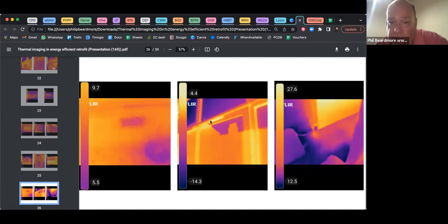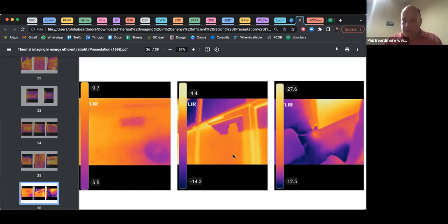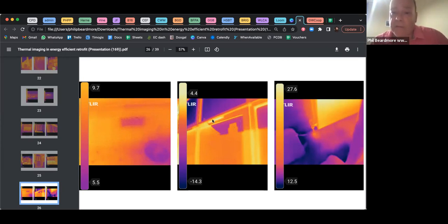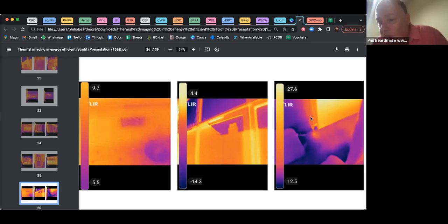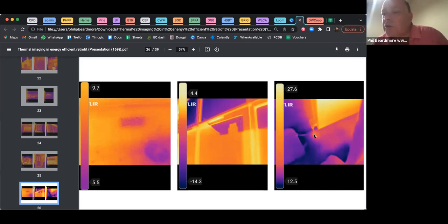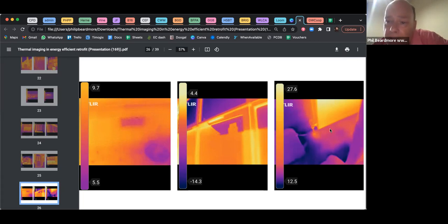This trickle vent image is taken from the inside — you have to be careful about reflections when doing internal thermal imaging involving glass. There is quite a lot of heat loss through that trickle vent. This is a radiator image from inside: the radiator is giving off heat as expected, but you can also see the floor is warmer near where the pipes come in and out — reflecting uninsulated pipework under the floor.